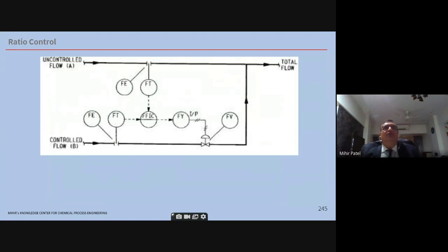Ratio control. Now for ratio control, in our last project we had put up a hydrogen plant, a typical example I am giving. Natural gas was the common fuel existing, going into the fired heater, and a hydrogen plant was put in additionally to make it green energy. So we were supplying 15% volumetric hydrogen into the natural gas line, and we put a ratio control on the hydrogen line. There was a control valve along with a flow transmitter on the controlled flow, which is the hydrogen flow. Natural gas flow was being measured, which is the uncontrolled flow. So suppose natural gas is 100 nm3, it will send a signal to the hydrogen FFIC to throttle the valve to 15 volumetric %. The control valve will throttle and you will get 15 nm3 going into the total flow. So this is the ratio control basically.